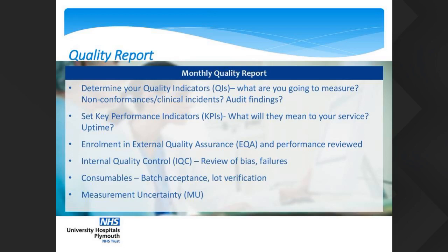The other thing we look at with the consumables is batch acceptance and lot verification. So we all know that consumables will change. The performance from manufacturing to clinical use can change between batches and between lot numbers that are produced. So you have to have a system in place to verify that. That may just be through internal quality control and calibration, but you need to state that within your quality system, within those documents that support your decisions, that is your approach, and it should be based on good science with clinical backup.